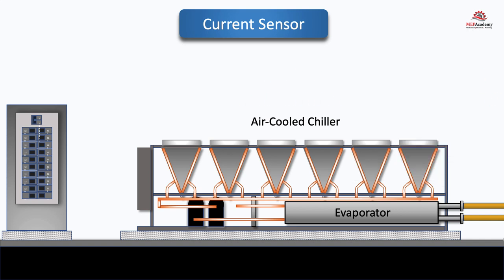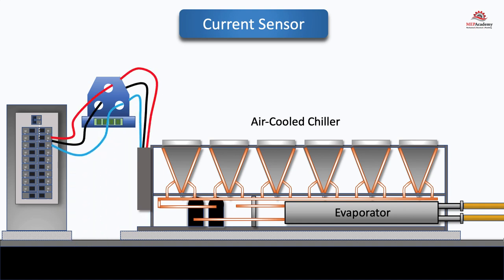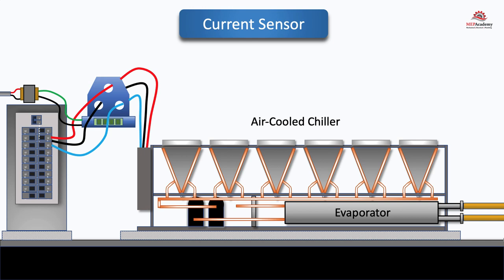Current sensor. A current sensor, also known as a current transducer, is used to measure the electrical current flowing through a conductor or piece of equipment. It plays a key role in tracking energy usage of equipment by monitoring the current draw. The current sensor is typically installed around the conductor carrying the electrical current of the equipment being monitored. The sensor may be a split-core design, allowing it to be easily clamped around an existing wire without interrupting the electrical circuit. The output signal of the current sensor is typically an analog voltage or current that is proportional to the measured current.